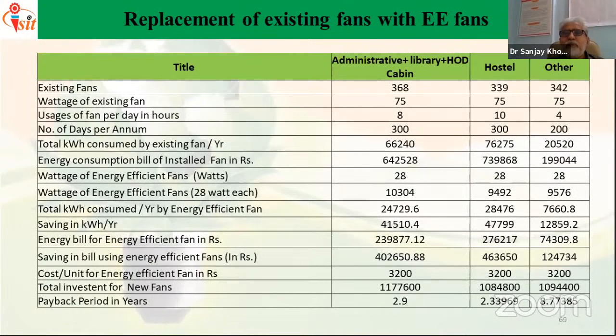Now this is an example for the fan. They have existing fans here, 368, 339 and 342. Existing wattage of the fan is 75 in all places. Usage of fan per day in hours: administrative is 8, hostel is 10 hours, and others 4 hours. We have considered this with the number of days per annum as 300 and 300. Total kilowatt hours, that is electric units, consumed by the existing fans per year, considering these 300 days, the number of fans and this capacity, comes to 66,240. Similarly, we have calculated for this.